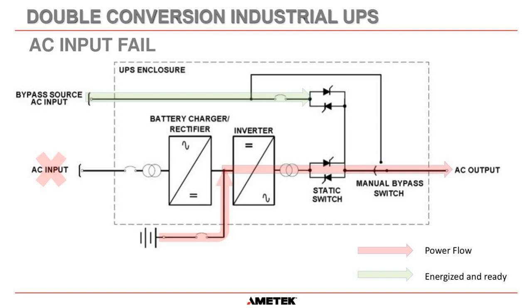So in a UPS, one of the most common things that happens is the AC input fails. Okay, that's why the UPS is there, just in case the plant has a power outage. And then what happens in that circumstance is the battery will continue to supply power to the inverter, and that DC gets converted to AC, and the output carries on regardless, as if nothing ever happened. Okay, we're still running on the inverter because the inverter is beautiful, clean, synthetically generated AC. It's a very clean sine wave and therefore very reliable.